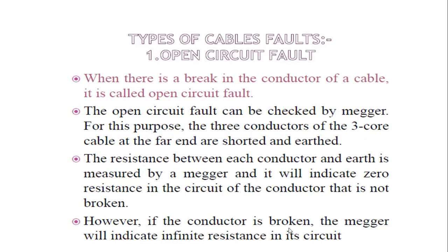However, if the conductor is broken, the Megger will indicate infinite resistance in the circuit. If the conductor is broken and we measure the resistance between the conductors and the earth using the Megger, then the Megger measures infinity resistance.